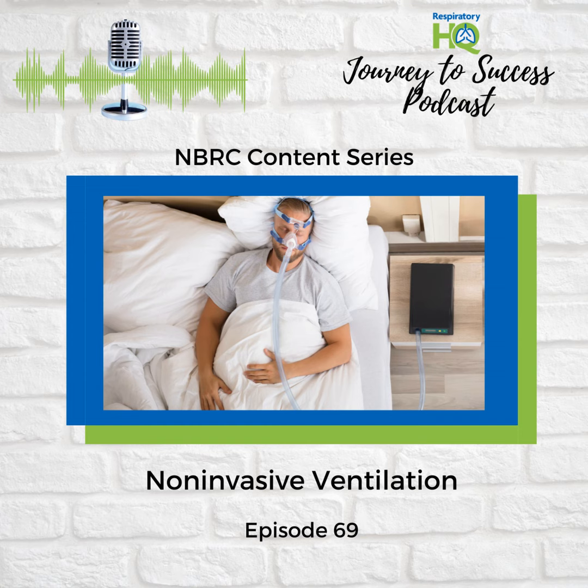And remember the rules. IPAP and EPAP can be the same, that's CPAP mode, but EPAP can never be set higher than IPAP. That wouldn't make physical sense. Got it. It really is a precise balancing act, isn't it? It absolutely is. Adjusting these pressures allows clinicians to really fine-tune the support, targeting whether the main need is for better oxygenation via EPAP or more effective CO2 removal via the IPAP-EPAP difference, or both.